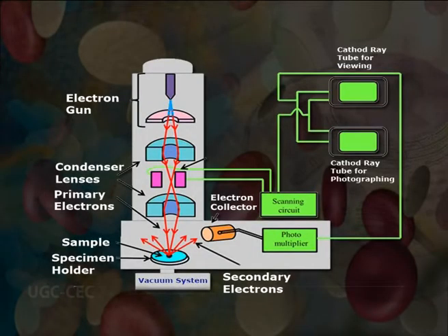In SEM, an incident electron beam is focused by the condenser lens system on the specimen to form a bright illuminating spot. The focus spot moves to and fro across the specimen in a rectangular grid pattern and generates secondary electrons, which are picked up by an electron collector, amplified and displayed on a cathode ray tube to produce a topographical view of the surface contours of the specimen.